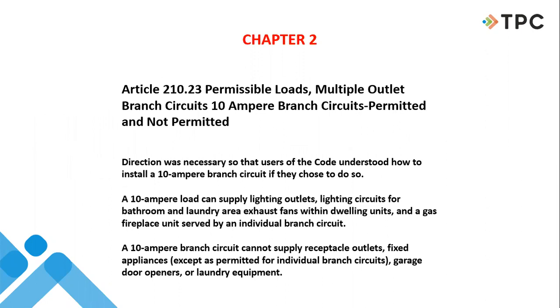Some direction was necessary. These 10 amp circuits. A 10 amp circuit can supply lighting outlets, lighting circuits for bathroom, laundry, dwelling unit exhaust fans, a gas fireplace. That's kind of what they were intended for. 10 amp circuits cannot supply receptacle outlets or fixed appliances, unless it's a specific individual branch circuit for one particular appliance, garage door openers, or laundry equipment. So in 210.23, they're just spelling out what a 10 amp branch circuit can and cannot be used for. Pretty clear.